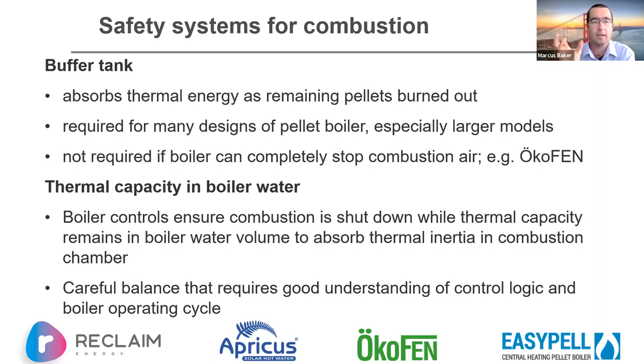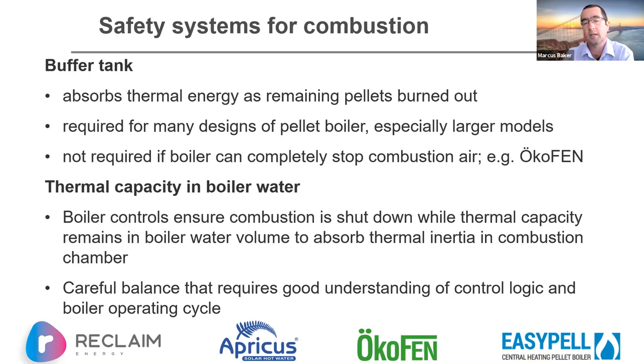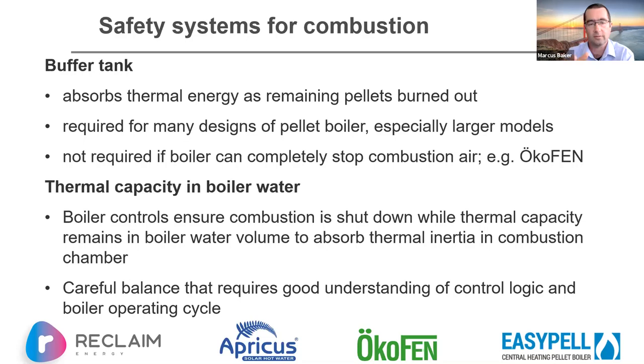Buffer tanks are actually required on many designs — ETA, Herz, and many others require one because they have a big burn chamber with a lot of residual fuel on a moving grate. If you've got a bed of embers and pellets, you've got to burn them out, and that heat energy must be absorbed. As models get larger it becomes more important due to greater thermal inertia. However, if a boiler can completely stop combustion air — the only example I know of is Ökofen, possibly Froling — then you don't need a buffer tank.